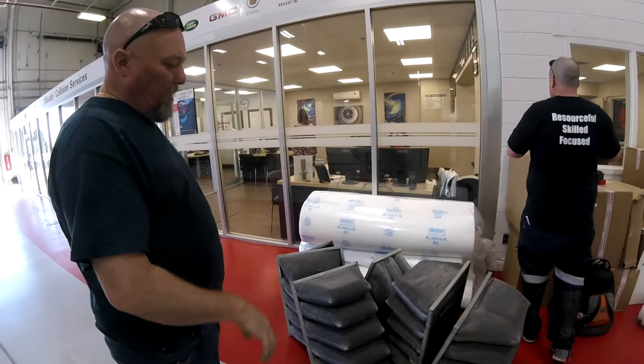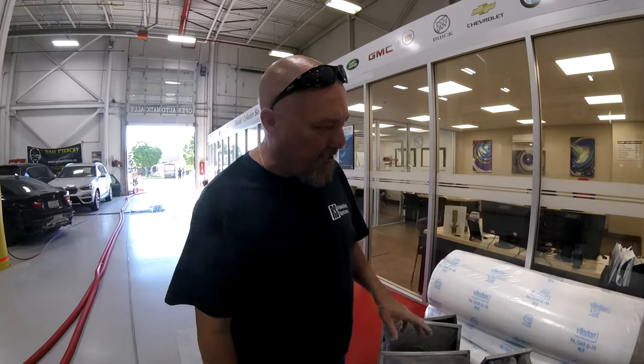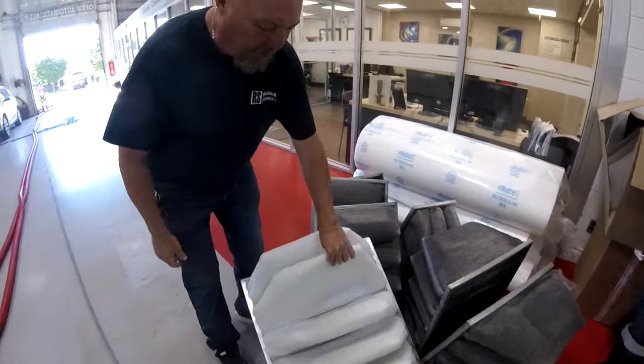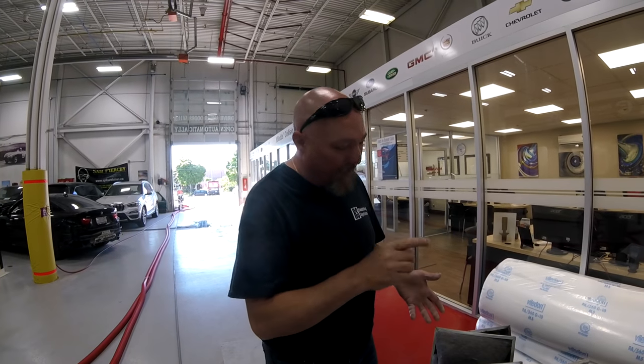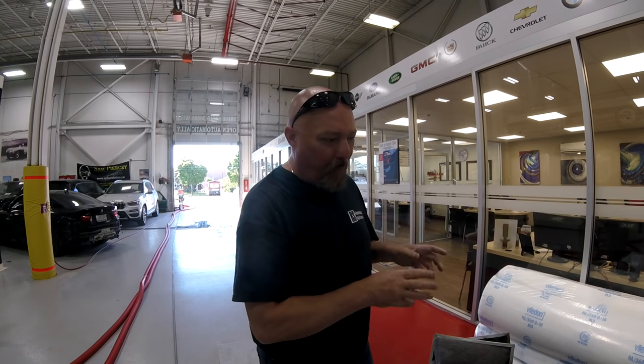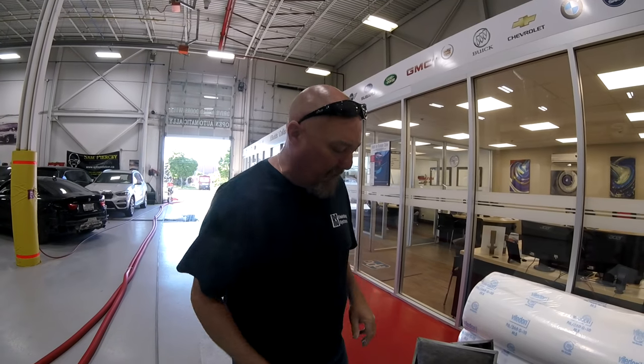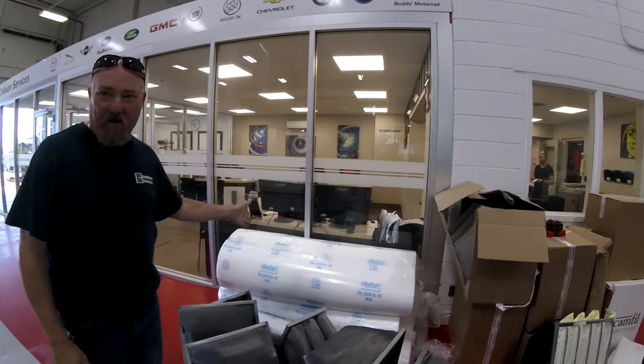These are your secondary exhaust filtration. It's very important to keep these cleaned — as you can see, these are really dirty, which is normal. You'll see what a new one should look like as opposed to the old ones. This actually protects your fans in the air makeup. That there is air coming in, and it's also air going out — the zigzag ones are gonna be pretty rock hard. This protects the main filters because they're obviously very expensive.